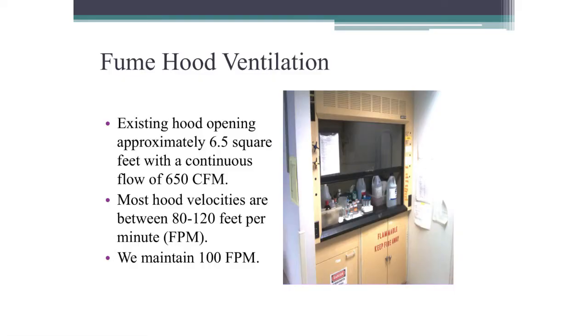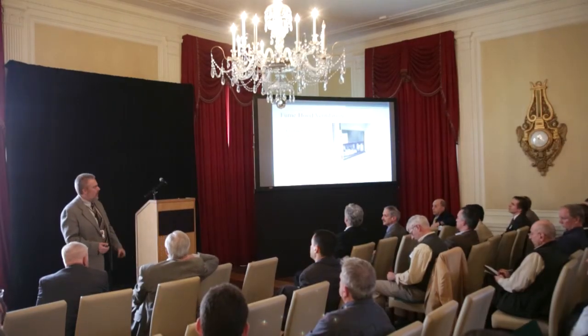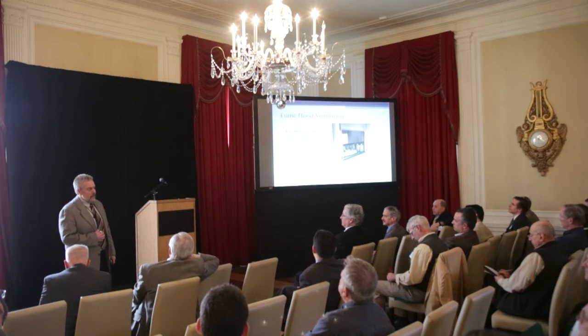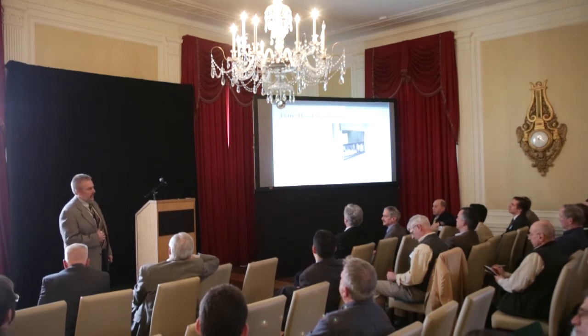So fume hood ventilation, we had a lot of constant volume fume hoods. And we said, well, how can we reduce that? Environmental health and safety says that we have to maintain 100 feet per minute. You guys all know it's between 80 and 120, depending on exactly what your requirements are. So we said, what if we reduce the open area? I know you guys were talking about actually closing the sash. We tried that for a long time. If it's not something that happens automatically, it's probably not going to happen.